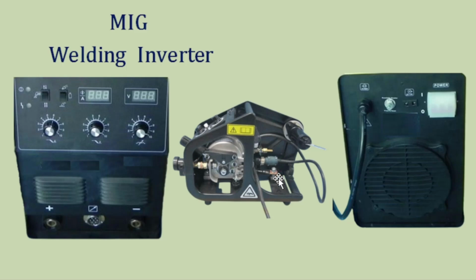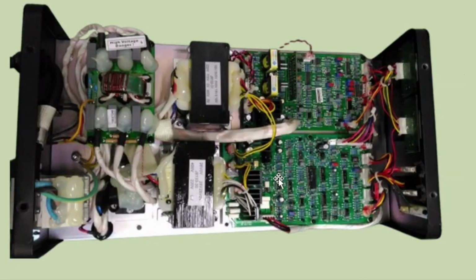Now coming to the inside components of the power source. We have removed the top cover of the machine. Input 3-phase power wires are coming to MCB. Output of the MCB 3-phase wires are going to input filter board. Here input filter is basically EMC filter. This filter is without power factor or harmonics correction circuits.